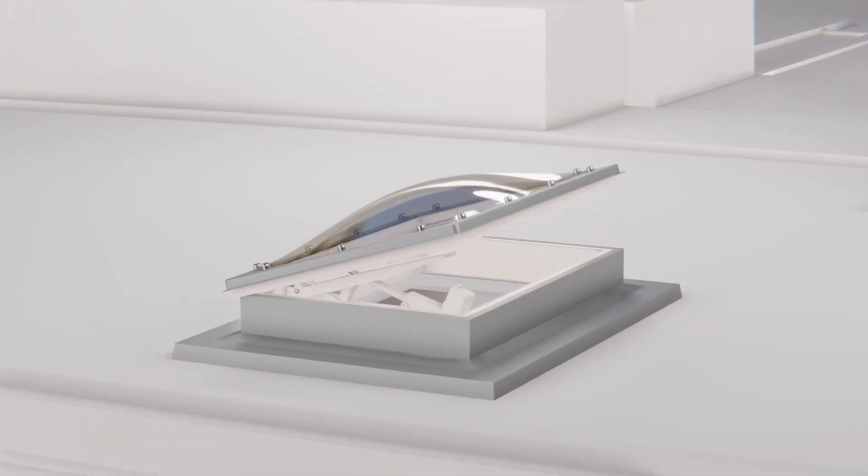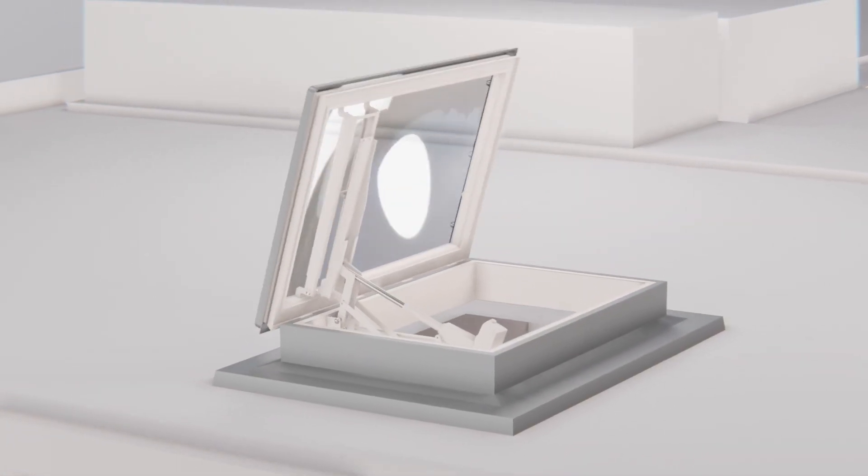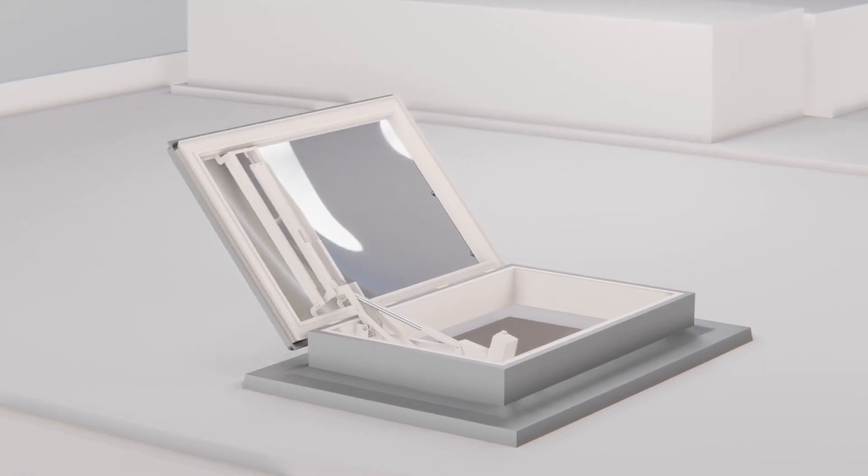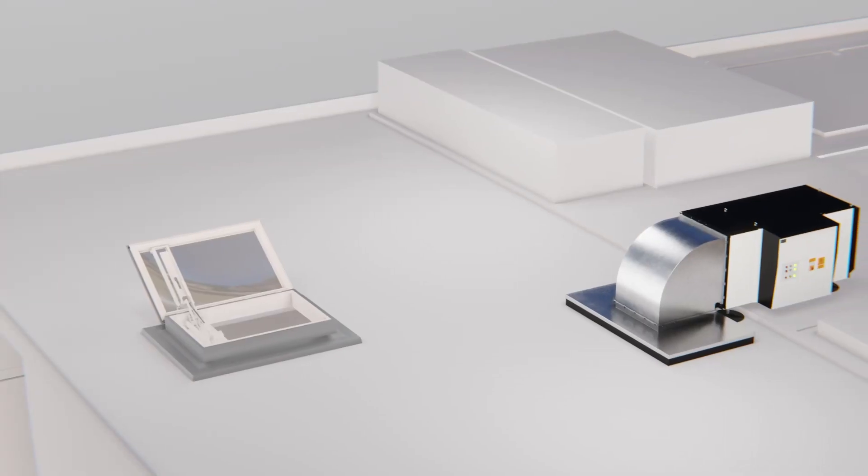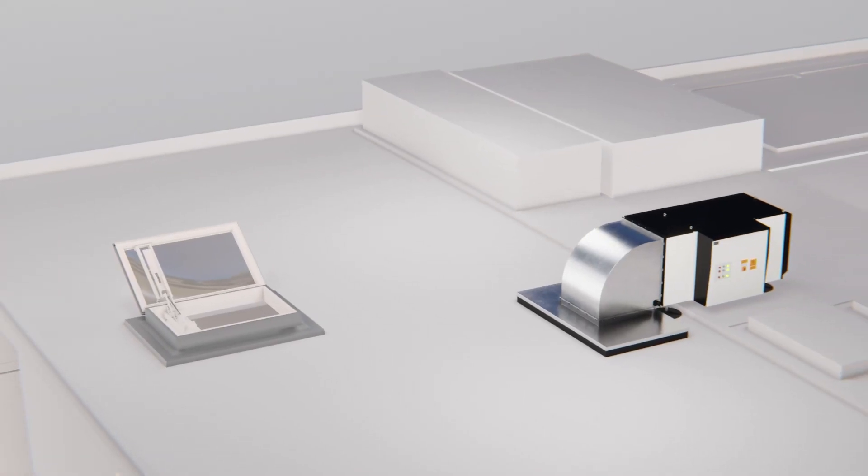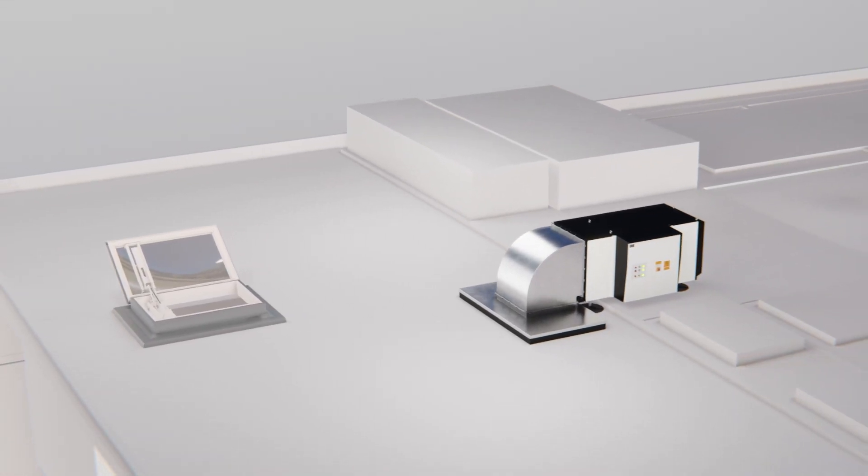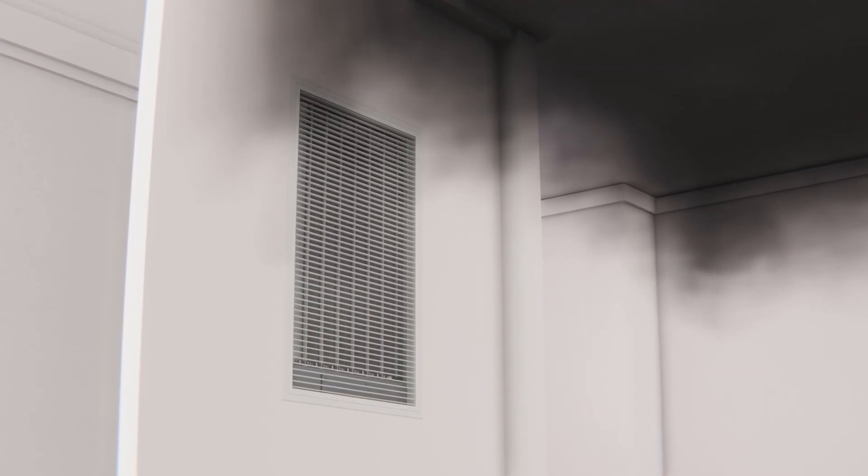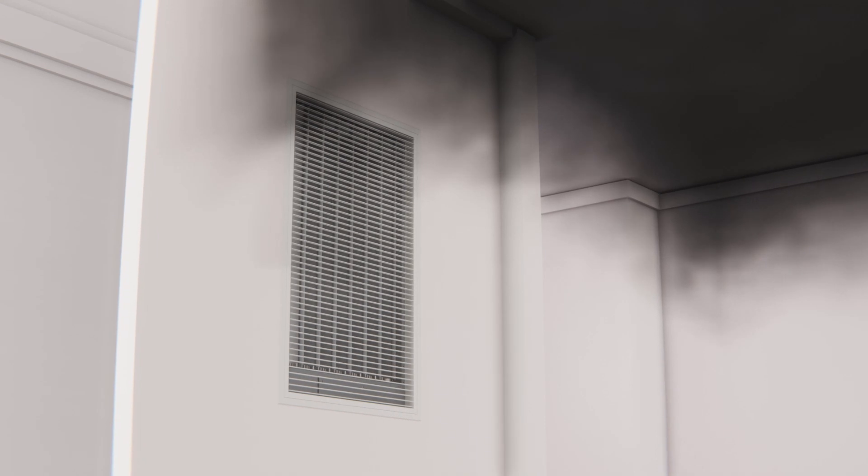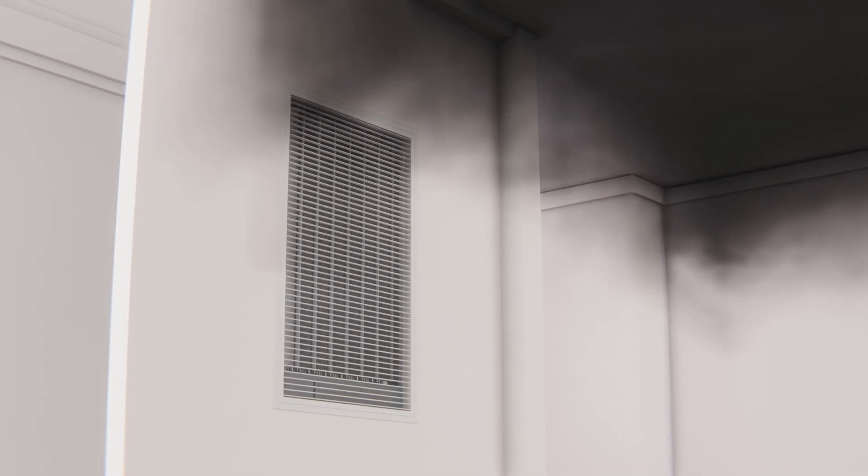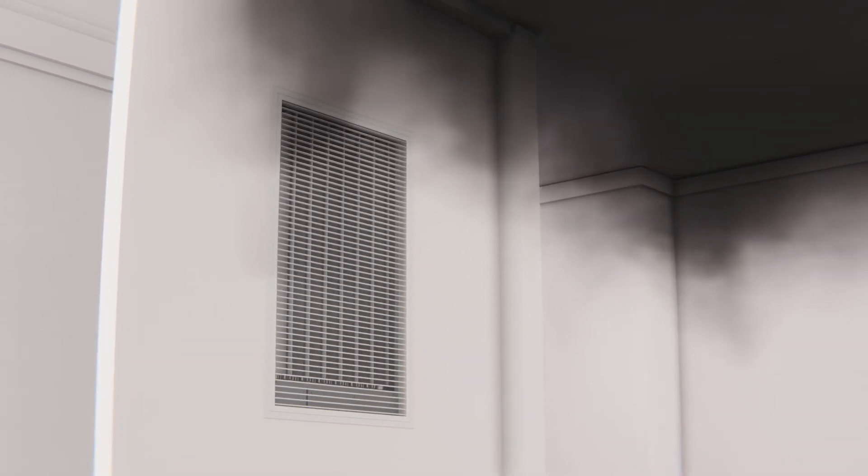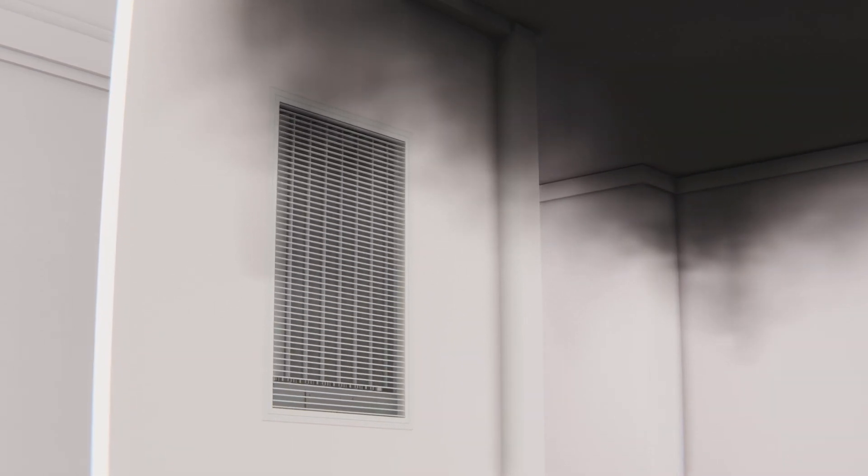The 1 meter square head of stair vent opens to provide a make-up air supply, followed by the damper on the floor of the fire origin. Every other damper locks shut.